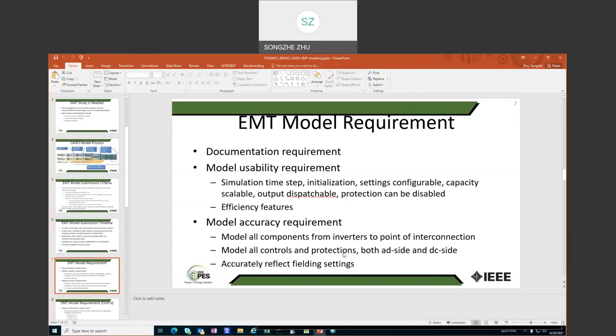Then the model accuracy requirement. We require the model be submitted for everything in the plant, from the inverters all the way to the point of interconnection on the grid. So all the devices should be modeled and should match what is installed in the field. And for the inverters, the model should include all the controls and the protections, both on the AC side and DC side. And then all the plant level controls should also be modeled. And all the controls and protections should accurately reflect their settings.